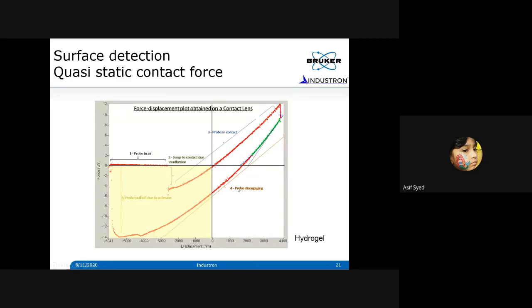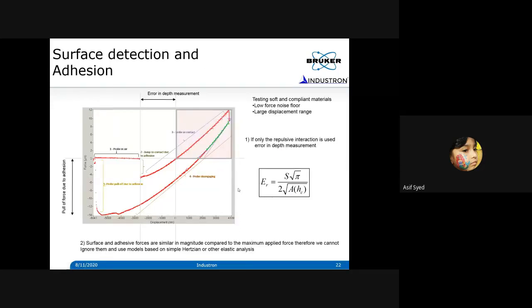The second part is, if you look at this curve, that's what I'm clearly showing over here, when the probe jumps to make contact, or the material jumps to make contact with the probe, at this point it happens. And then normally what we say is the zero point is where we start to see the repulsive interaction, the positive force, and we define that as the zero point. And the probe has already penetrated into the sample almost 2,800 nanometers, 2.8 microns, in this particular case. Okay, so this much error in depth measurement is there in your measurement. So whatever property you are going to measure may not be accurate.